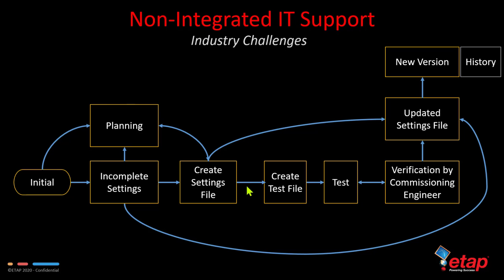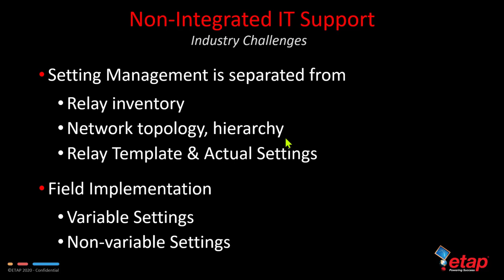Here's another portrayal of the life cycle of the protective device settings, where the planning department can provide the initial settings, and then create the setting files. They will create a test file, test, and then the test is verified by a commissioning engineer who then updates the setting file and a new version is created. And this previous version or the initial version is converted into a history. So again, this process tends to be somewhat manual and involves a number of data entries, double entries, as well as passing of documentation that might be in Excel or other formats.